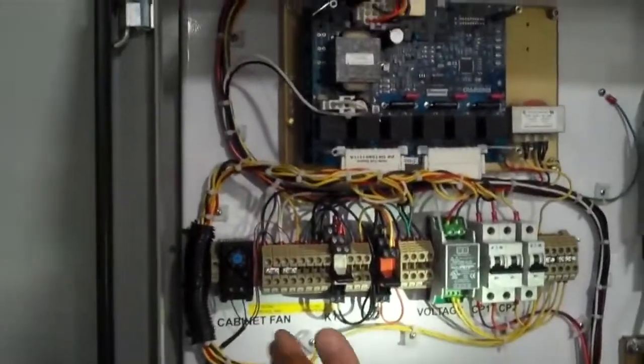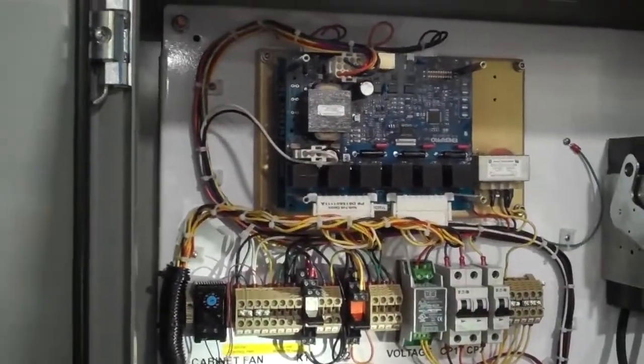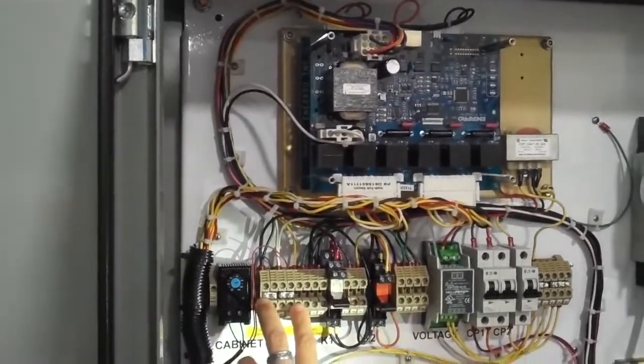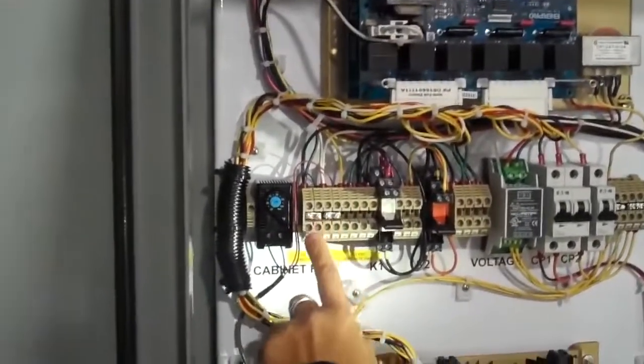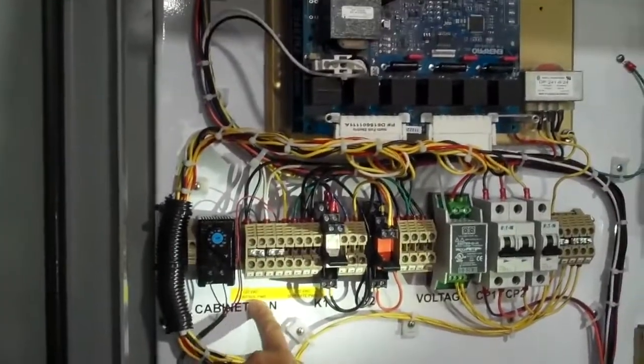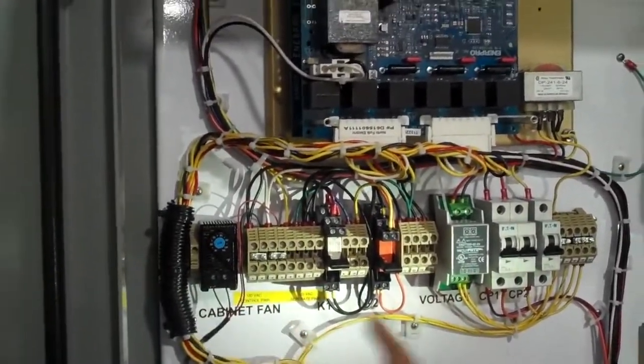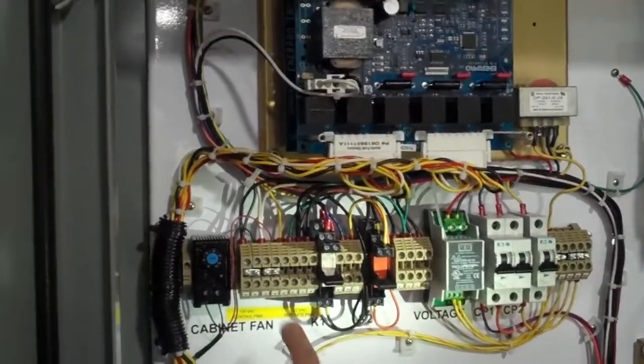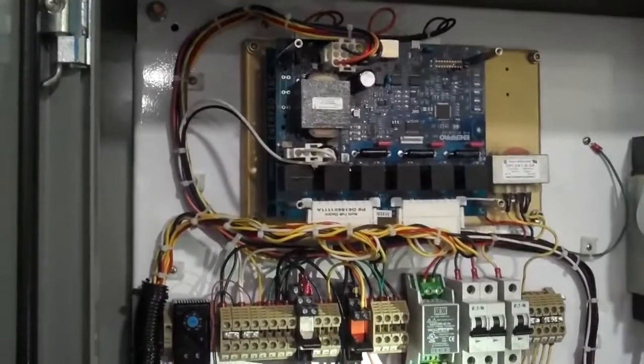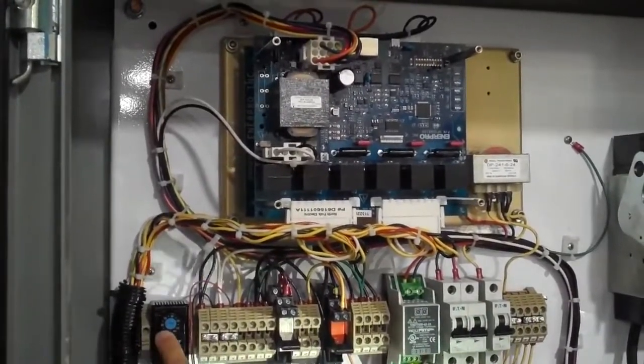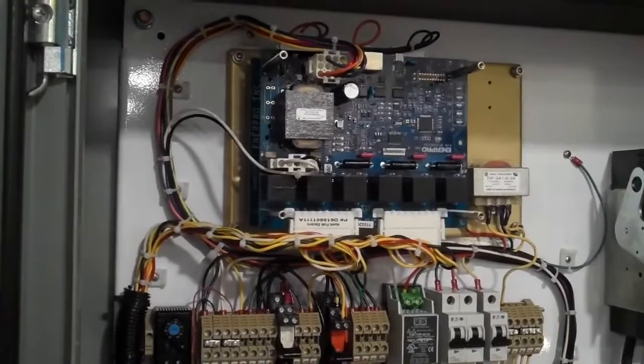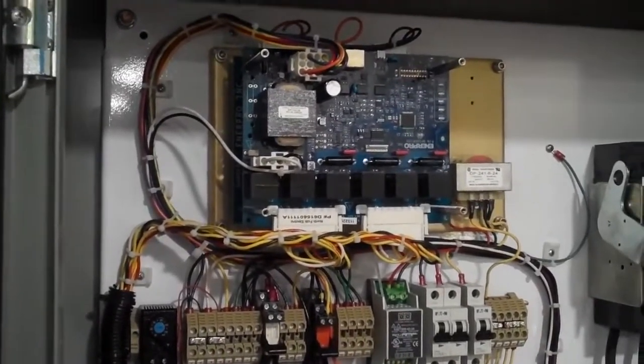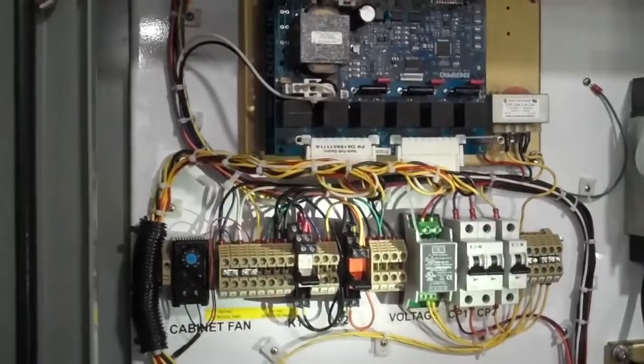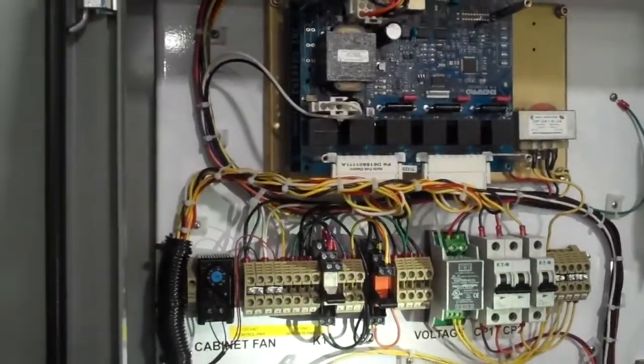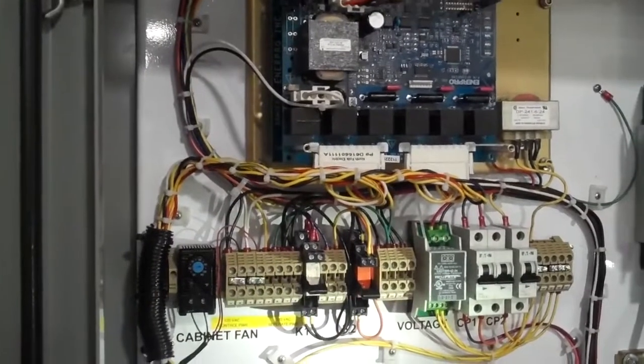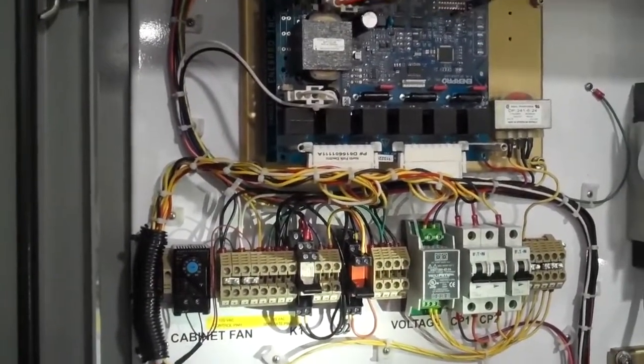Now, going through this terminal block, the first 4 positions are allocated to the 120 volts AC for control power, and out of this 120 we power 3 devices. We power the firing board, we power the cabinet fan that can be controlled through a thermostat, and the bridge fan that is controlled by a thermostat. Once that thermostat, normally open at room temperature, reaches a temperature of 60 C, it will close and the fan will enable.